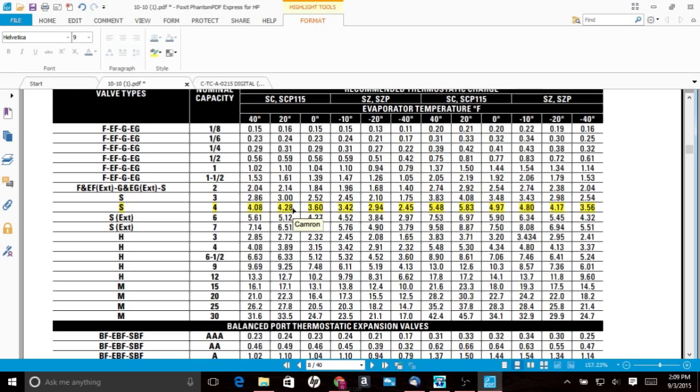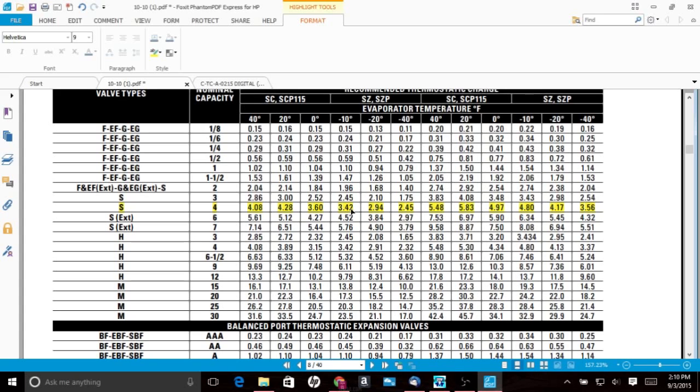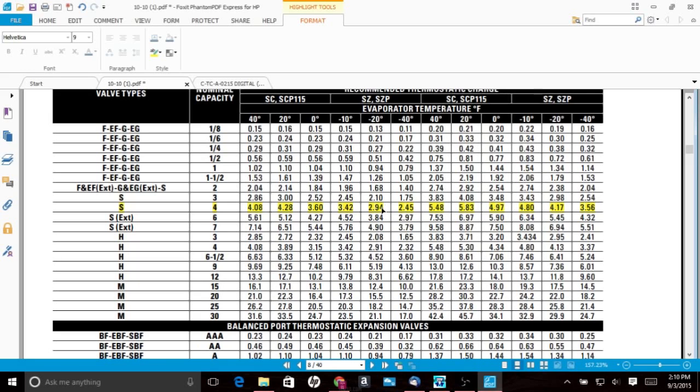So you would have, you're looking at a medium temp application for that. And it derates to 3.42 tons at minus 10 and 2.94 at minus 20. They're right at the knife edge of, you know, whether it's going to work to its full capacity or not at, you know, peak conditions, highest load conditions.